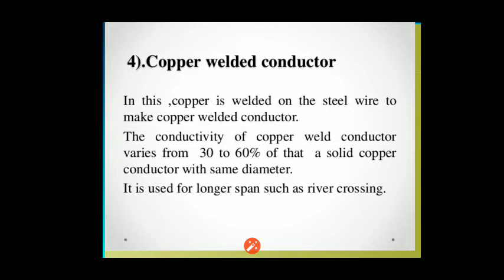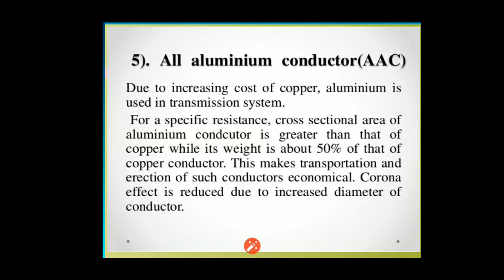Fourth, the copper welded conductor. In this type, copper is welded onto steel wires to make the copper welded conductor. The conductivity of the copper welded conductor varies from 30 to 60 percent of that of a solid copper conductor of the same diameter. It is used for longer spans such as river crossings and end-of-line applications.